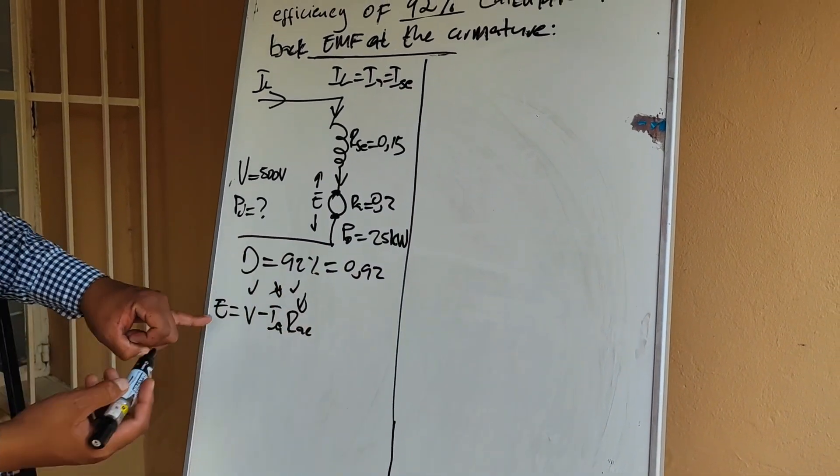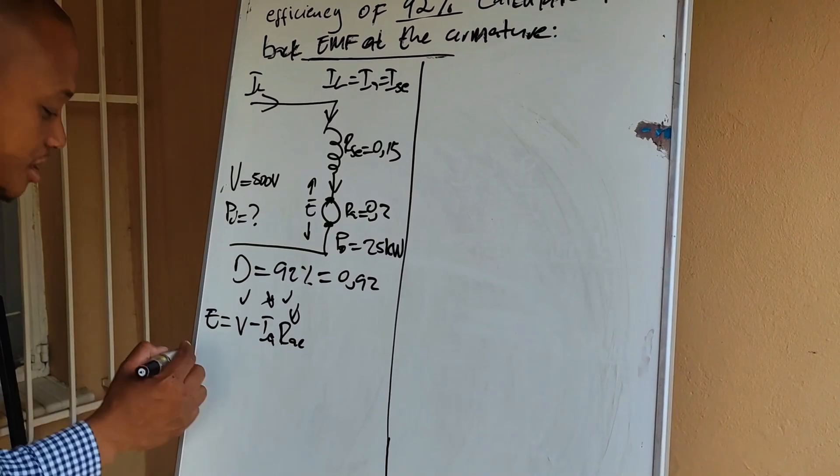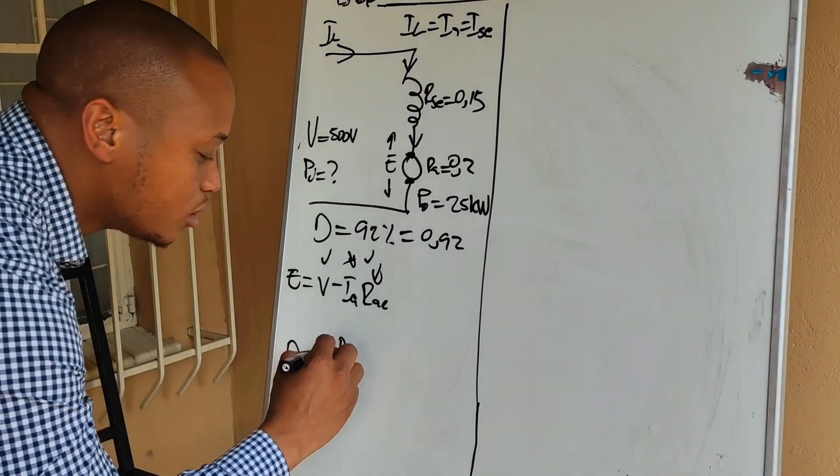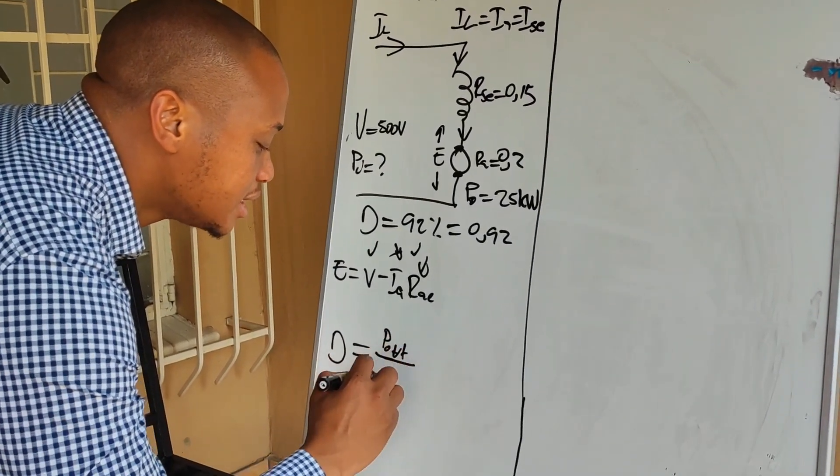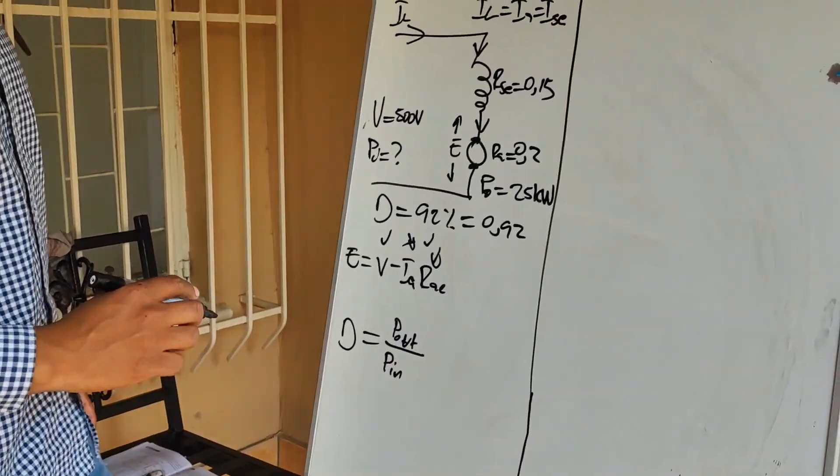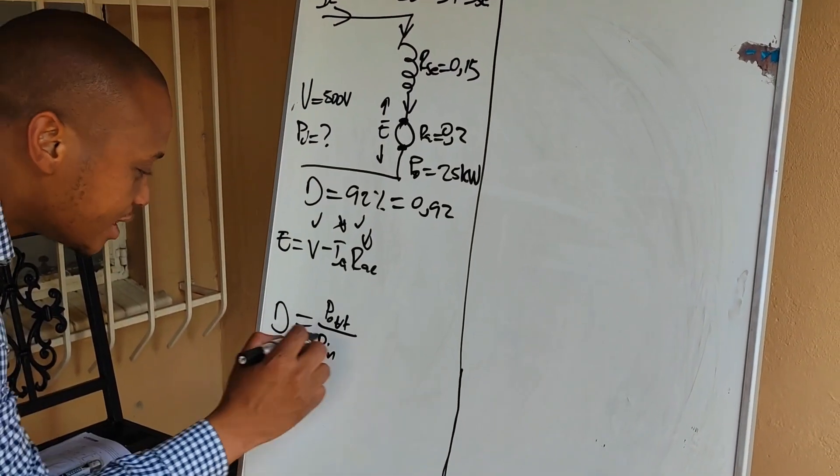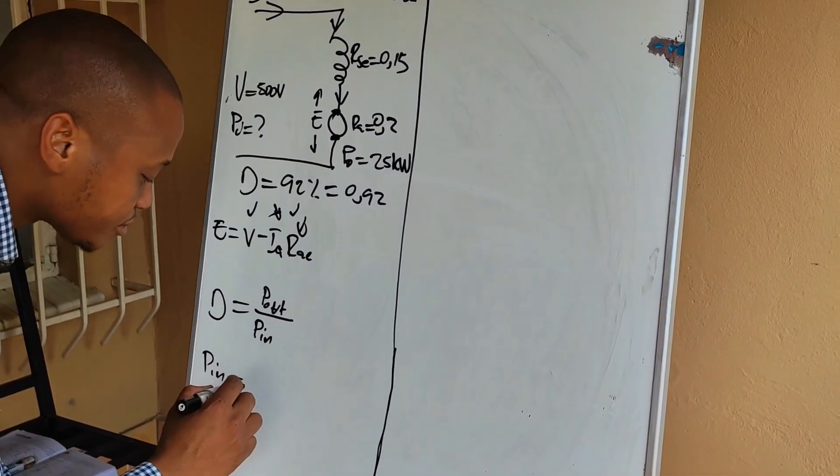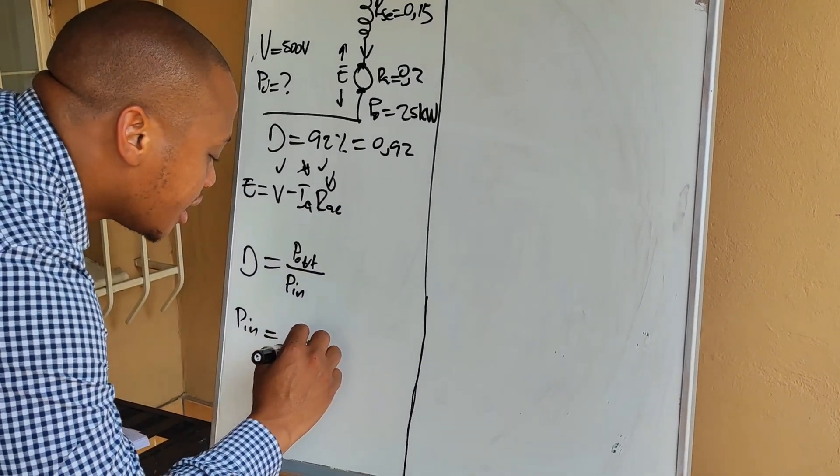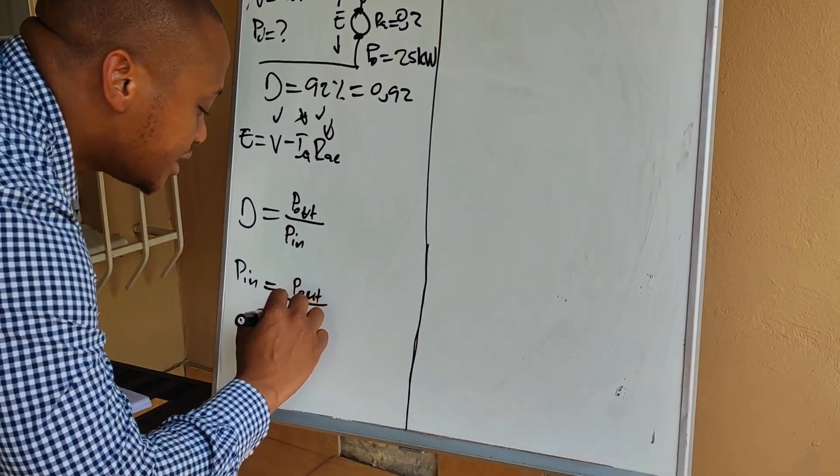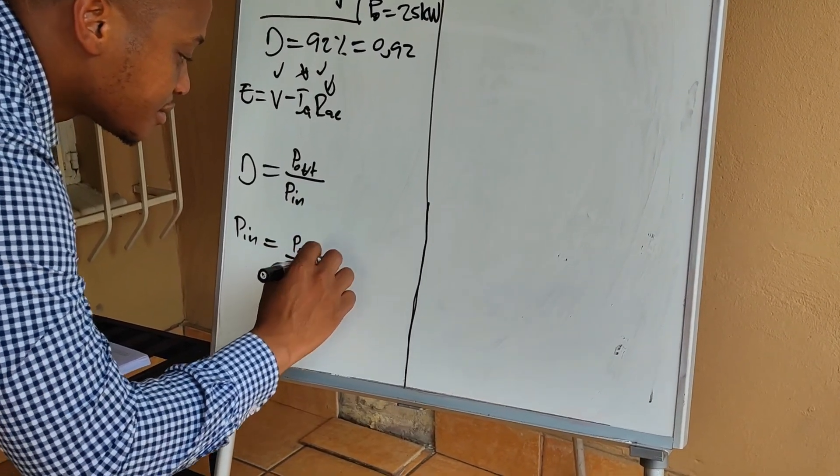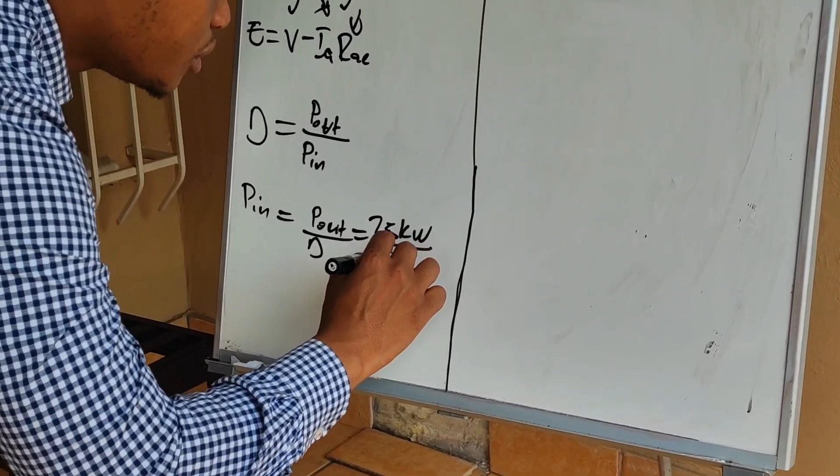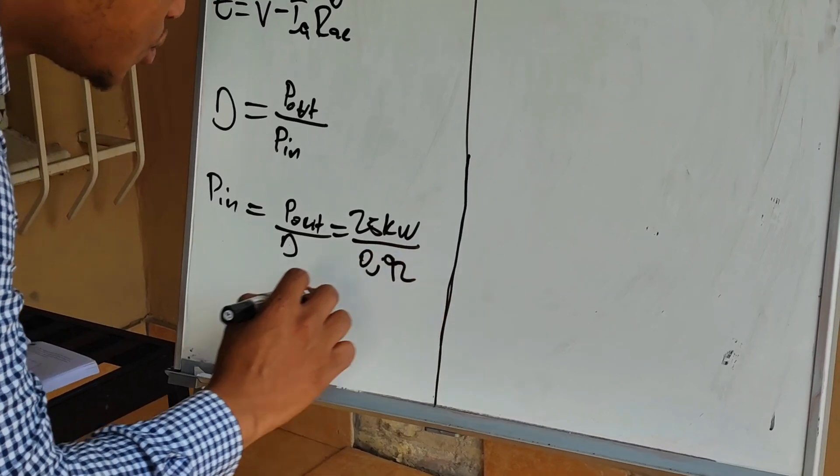But I am given an output power and an efficiency. That means I can say the efficiency of any operating machine is equal to the output power P out divided by P in. So I can then calculate the value of P in which is equal to P out divided by the efficiency which is equal to 25 KW divided by 0.92.